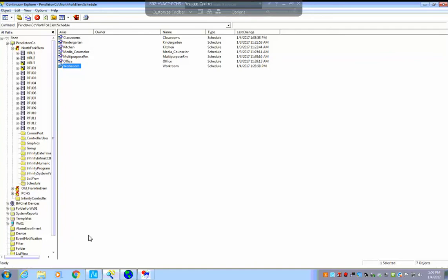But anyway, over the holiday, close to the 1st of January, I've dealt with some schools that had a significant number of different schedules for the rooftop units, 10 or 12 schedules for a site. So to put in the new yearly schedule of holidays and such, it was quite cumbersome. And I know there's a mass update feature on the schedule of these things, so I wanted to show you how that worked.